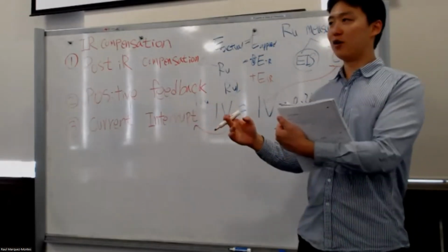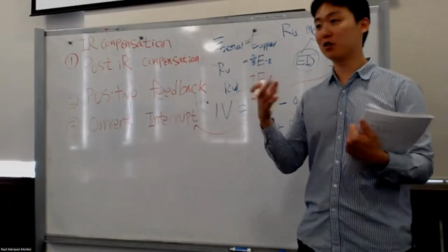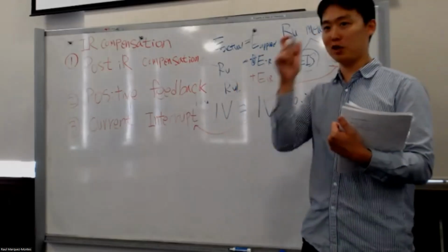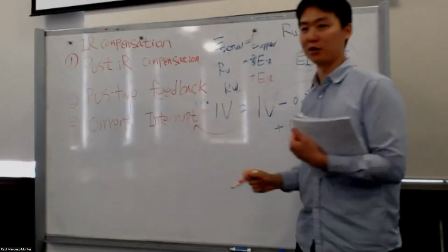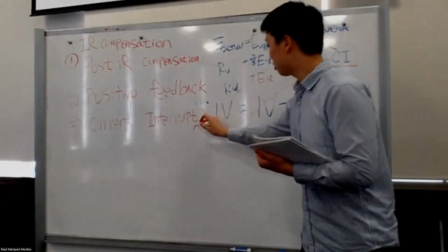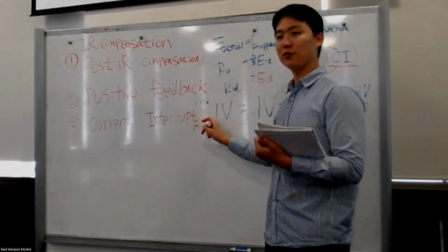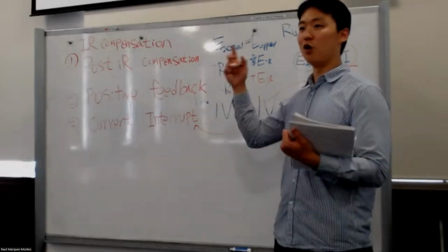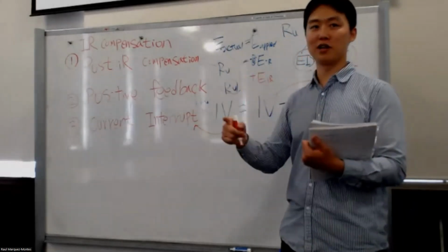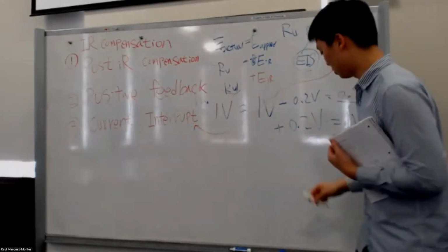So if the RU value changes during the electrochemical testing, we can track how the RU value changes and immediately reflect that value. So for this current interrupt mode, if we click this current interrupt mode for the IR compensation using our software, we don't have to measure the RU before our analysis. It will automatically measure the RU during the analysis and do the IR compensation immediately. Okay.